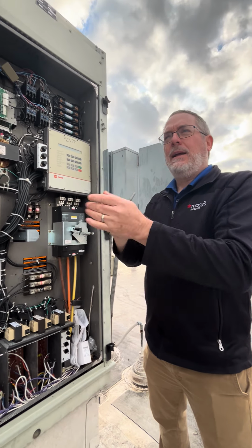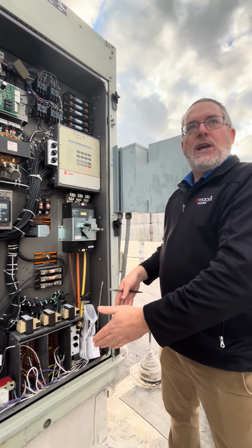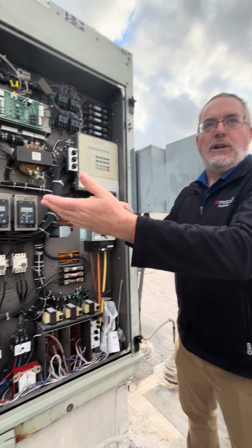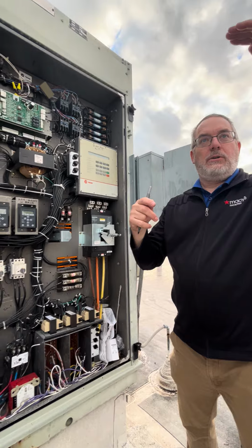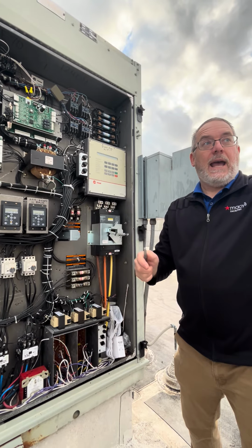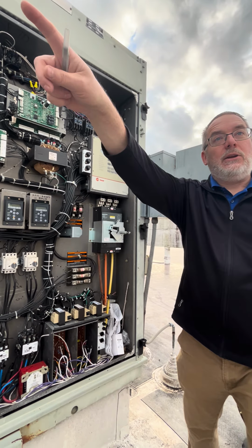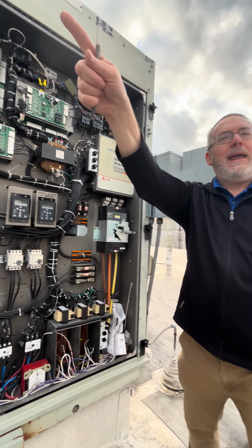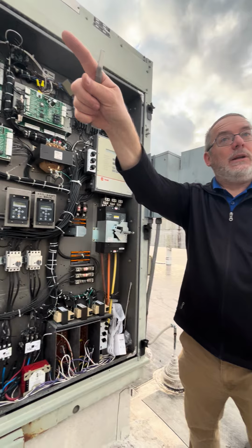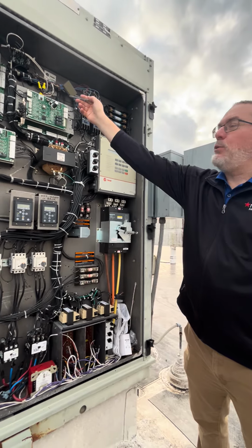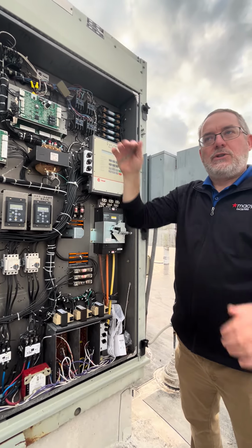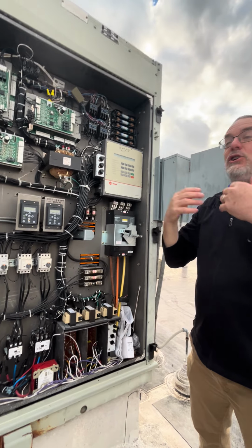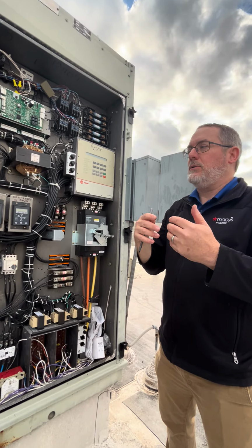Some will go 90. Maybe this unit serves center core, cosmetics, and you just can't ever keep up, so we let them run at 100. You'll see some stores that run at 100. This unit might be at 100. That unit might be capped at 90. That unit is in second floor furniture. Nobody's ever up there. There's no heat load. Maybe 80 is fine on that unit. Again, that's all in software because we control the drive directly. So you can balance your airflow a little bit like that, or in deliverable cooling BTUs.